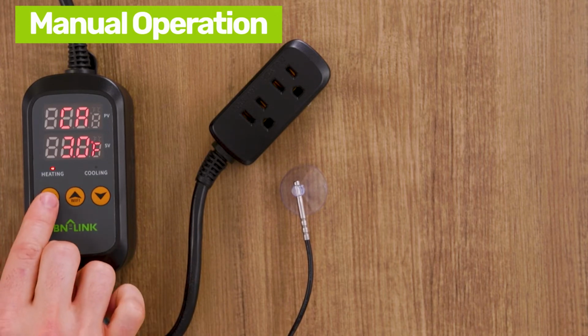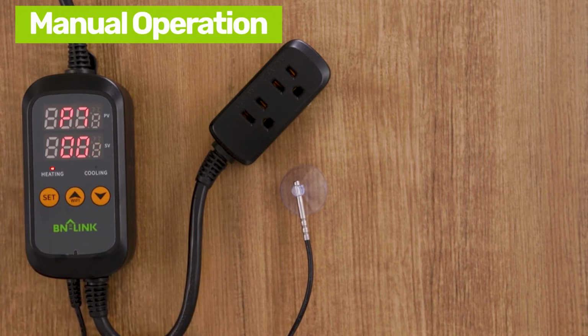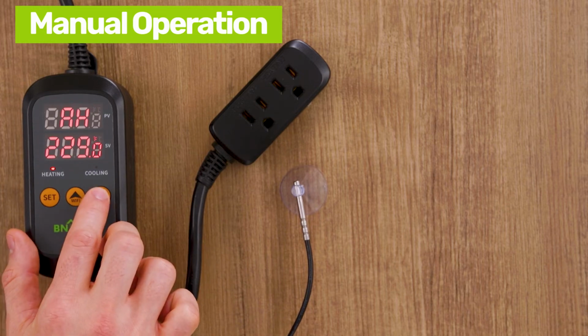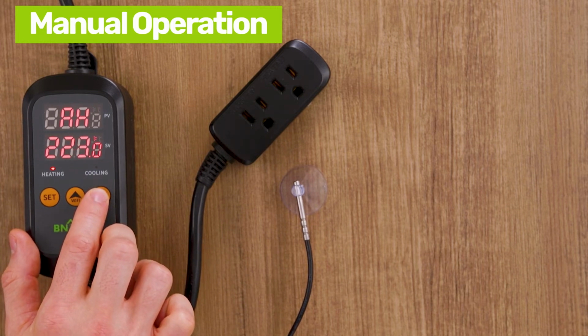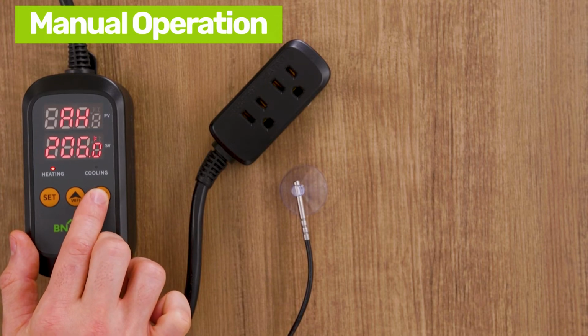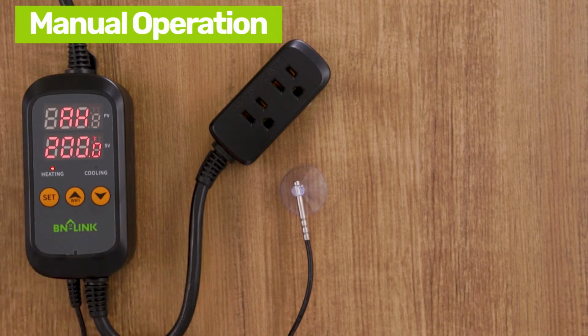Press Set once again and see the PT menu. The PT menu is a compressor time delay and defines a time interval of 2 compressor cycles. Press Set again to go to AH, which is for the high temperature alarm. Set this temperature so that if the temperature exceeds the AH, an alarm will go off. To stop the alarm, simply press any button and the beeping will stop.